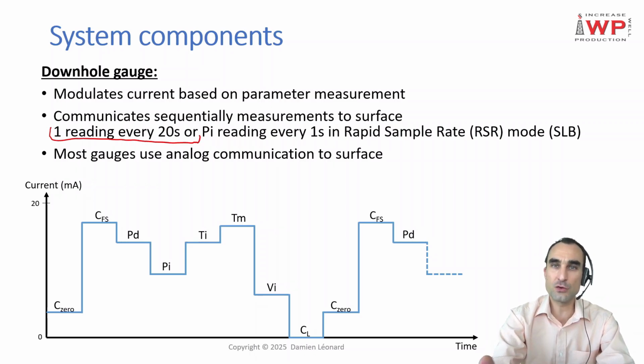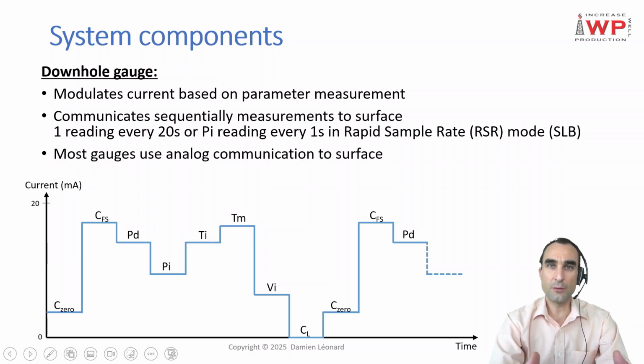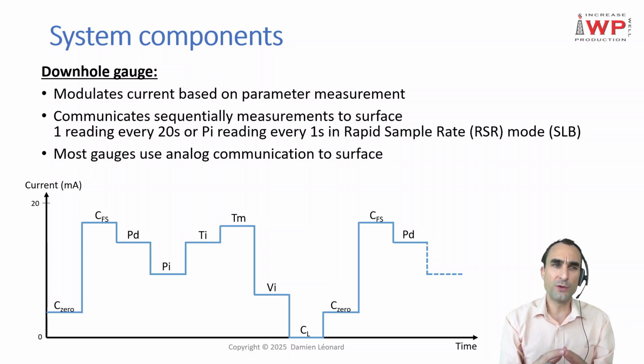In the case of Schlumberger gauges, for instance, it is every 20 seconds, but this can vary from one supplier to the other. For instance, with Leva, it's about every 15 seconds that you will have one new reading of a sensor. I took a look at Alkorayef. They've got the Spectrum Advanced Ground Fault Tolerance ESP monitoring system. With their gauges, they are able to communicate new values every 2.5 seconds. So that's a lot less. As you can see, this duration can vary from one supplier to the other, from one gauge to the other.